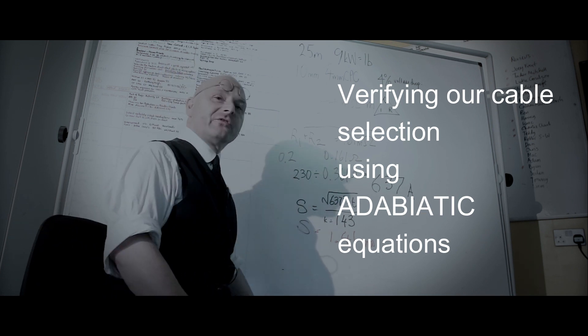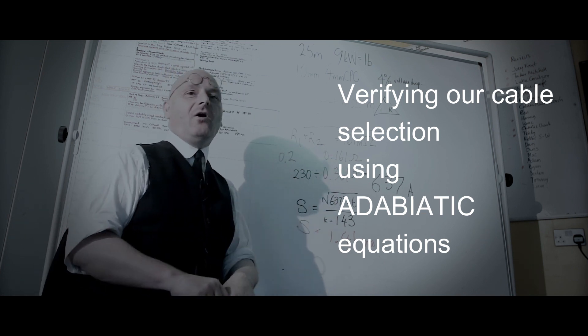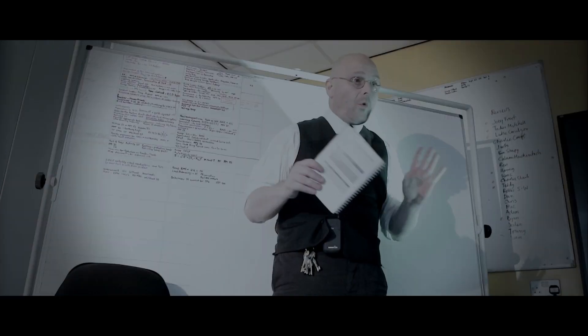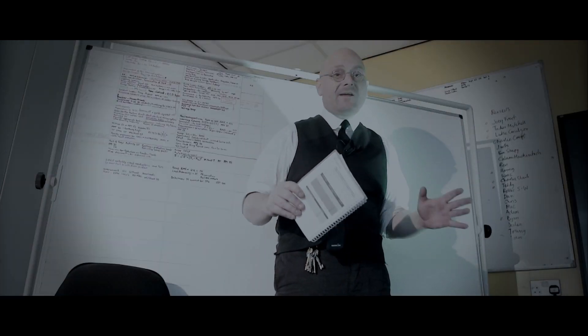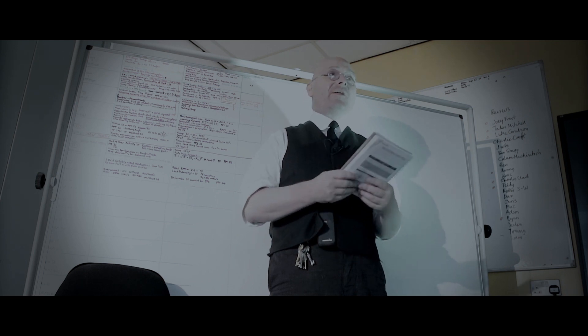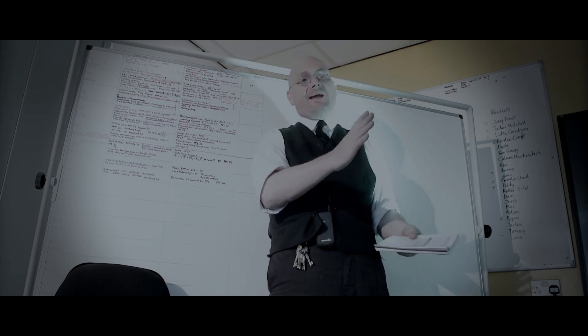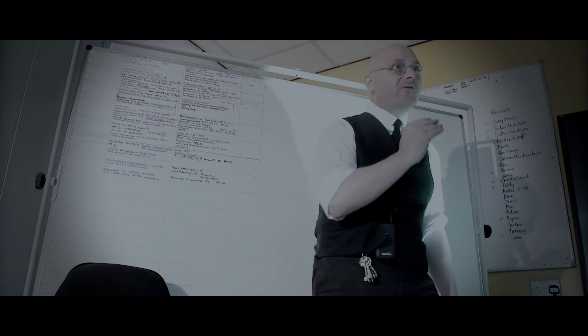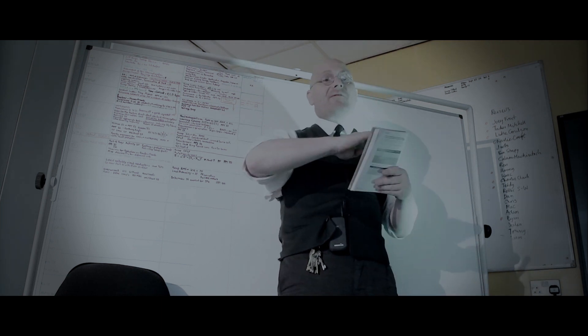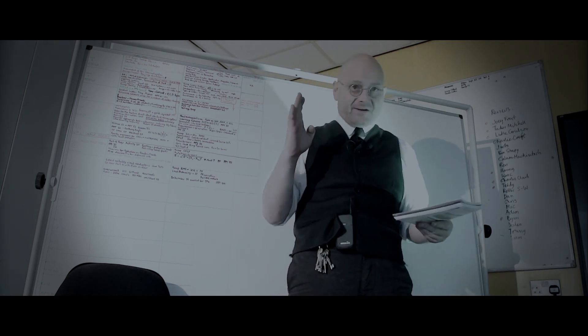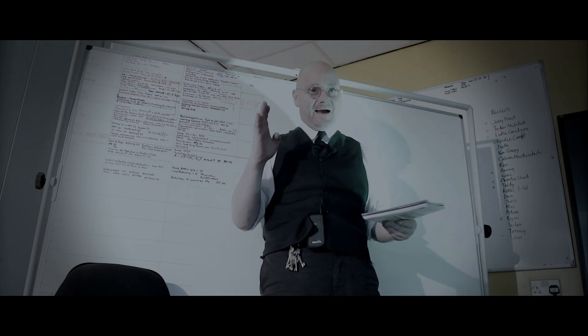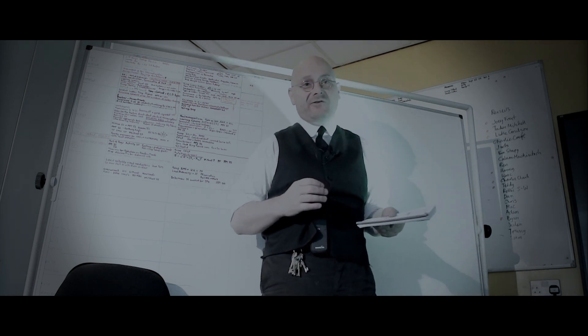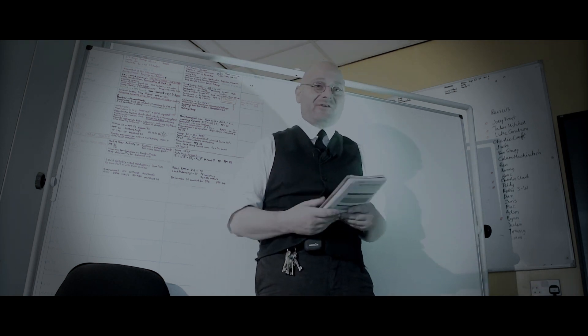Here it's used for safety of designed circuits. Whatever combination we're using, we need to work out that the CPC, during the period at which the fault current of hundreds of amps flows down it — before ADS, automatic disconnection of supply, happens — whether the heat buildup in that cable is going to be enough to damage the insulation.